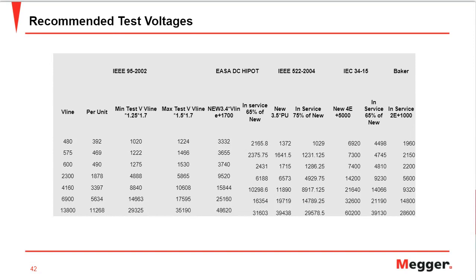IEC is a European standard, which is, of course, more used in Europe. And then there's the Baker standard, or we can say, just to calculate the test voltage with reference to the rated terminal voltage of that motor, we can use something simple and straightforward: you multiply the rated voltage by two and add 1000 to it. So there are different motor rated voltages, and then again, as per the various standards, if it's a new motor, if it's in service, what test voltage should we be using to do high-pot and surge testing?